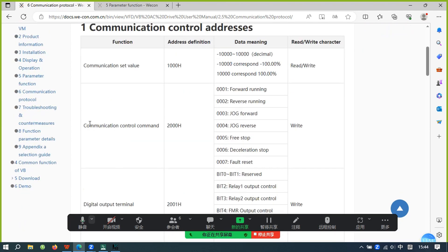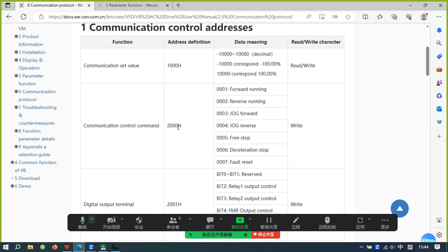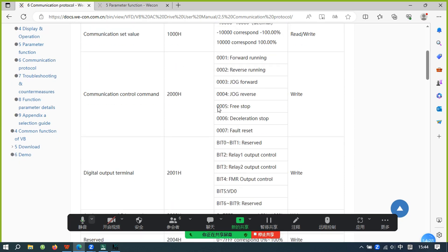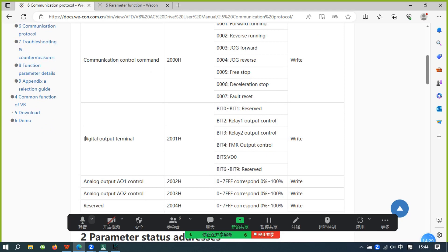The communication control command address is 2000H. This address controls the operation of the inverter. For example, if you give the value 1, the inverter will be in forward running. This is also related to the digital output terminal.